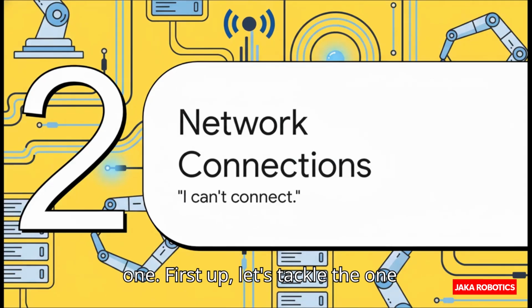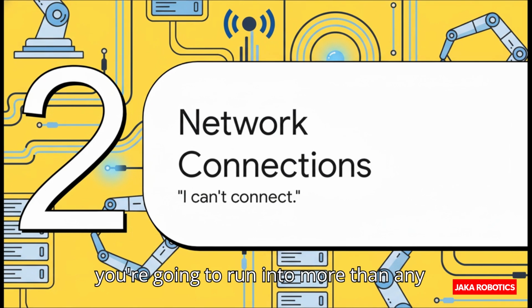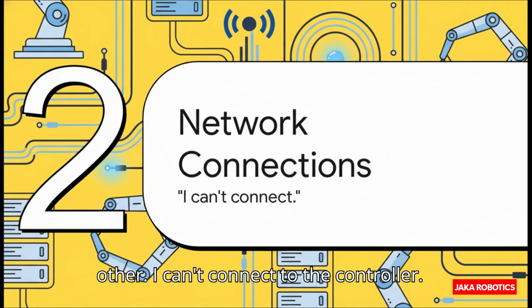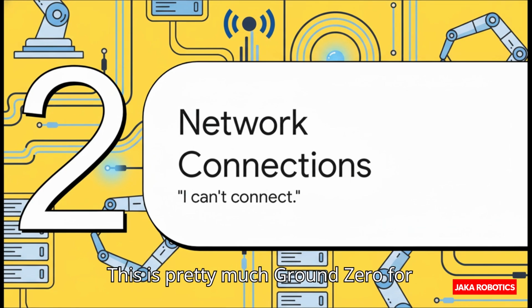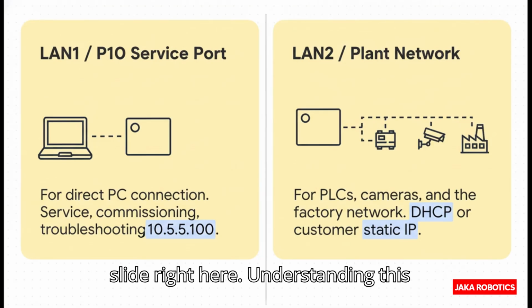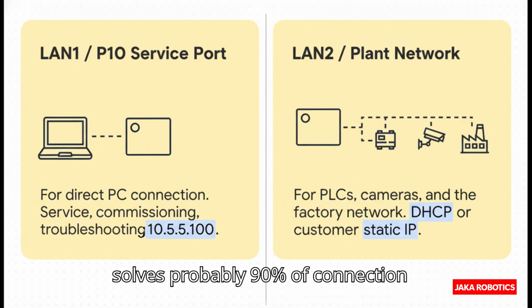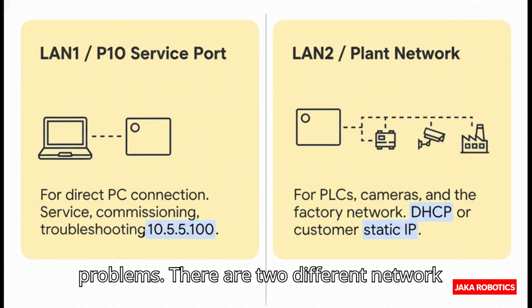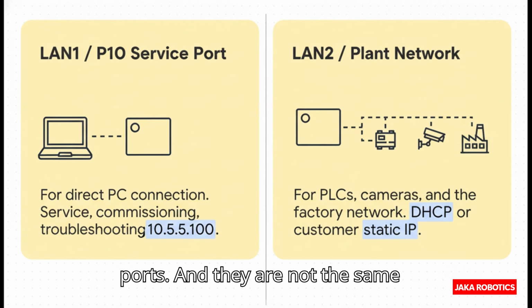First up, let's tackle the one you're gonna run into more than any other. I can't connect to the controller. This is pretty much ground zero for almost any service call. Honestly, this slide right here, understanding this solves probably 90% of connection problems. There are 2 different network ports, and they are not the same.